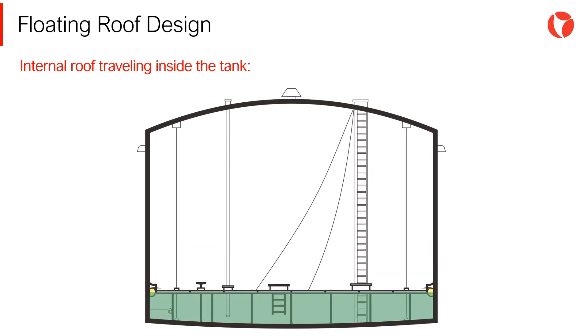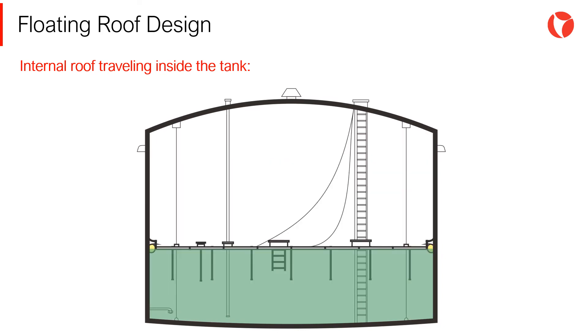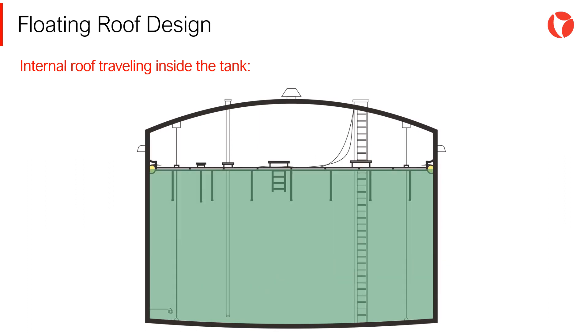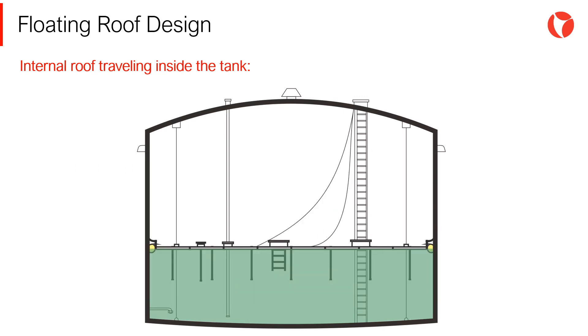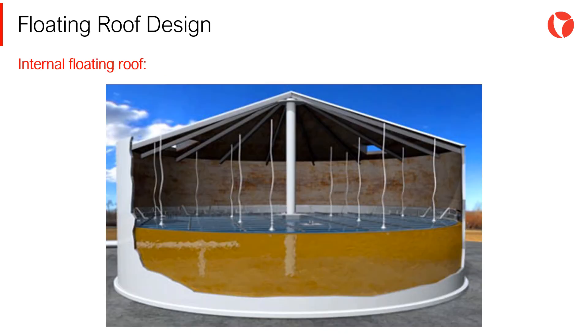The net capacity of the tank is limited by the total distance that the roof can travel within the tank. The lower limit depends on the arrangement of the tank in terms of internal pipes and connections penetrating the tank wall. Internal floating roofs can directly rest on the stored product, so there is no vapor space between the roof and the product. The free space above the floating roof must be adequately vented to the atmosphere to avoid the accumulation of potentially explosive gases.